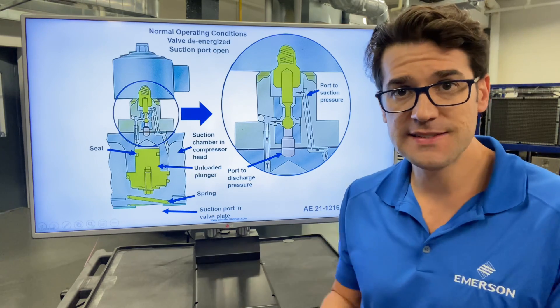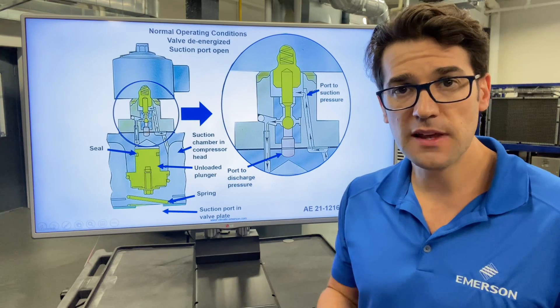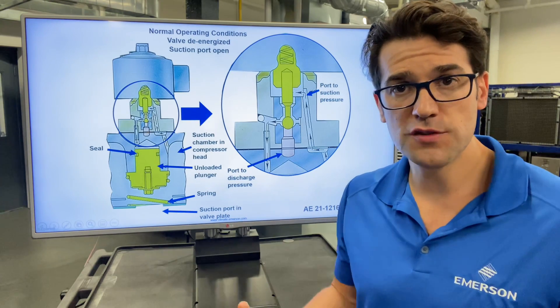On our 4D and 6D compressors, we have something called unloaders, block suction unloaders. What they do is they block the suction so there's no compression happening.